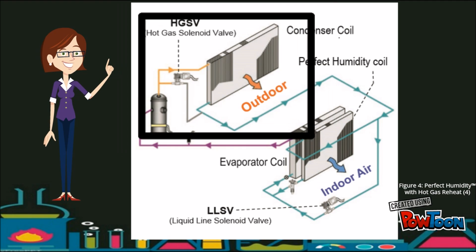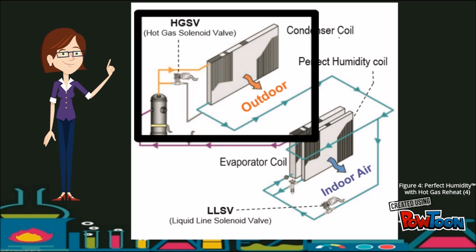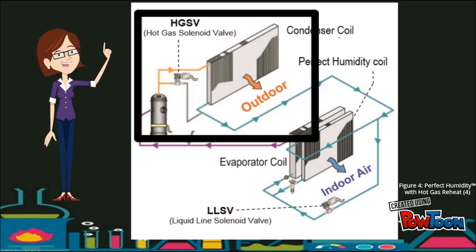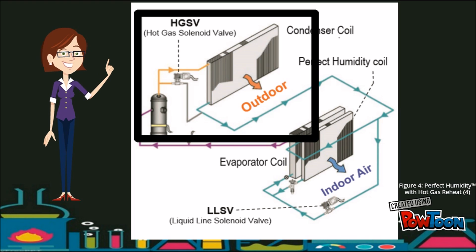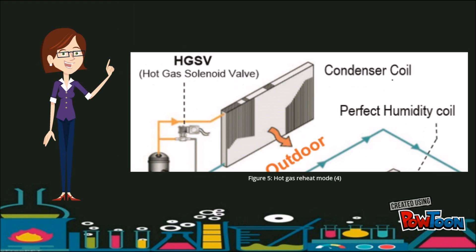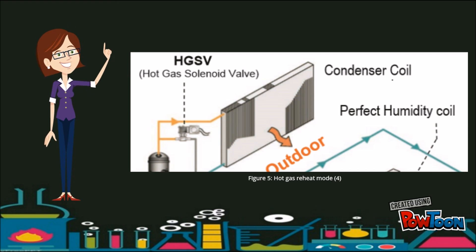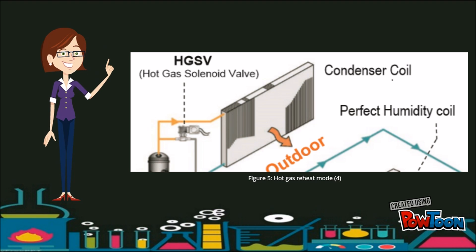At this point, it is mixed with the sub-cooled refrigerant leaving the condenser coil. This two-phase mixture is routed through the perfect humidity coil and then the evaporator. Additional sub-cooling occurs in the perfect humidity coil. When this refrigerant is fed into the evaporator, the result is a colder coil surface. The air is cooled and dehumidified as it flows across the evaporator.